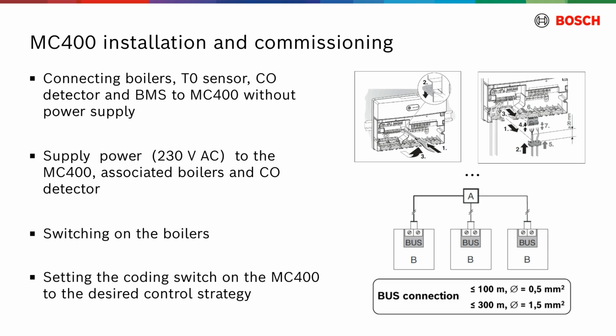The MC400 module will detect the connected devices. Depending on the number of devices, this can take up to 5 minutes. During this time, the controller will not respond to heating commands. As soon as the first device is detected, the MC400 activates the power supply on the system bus.